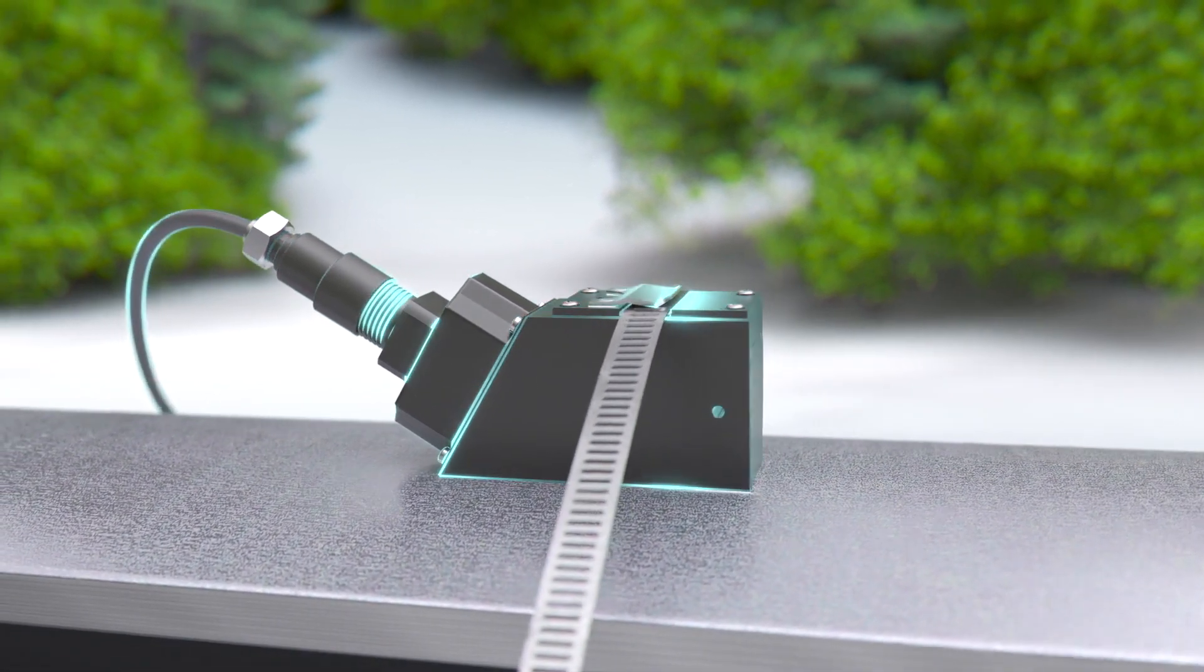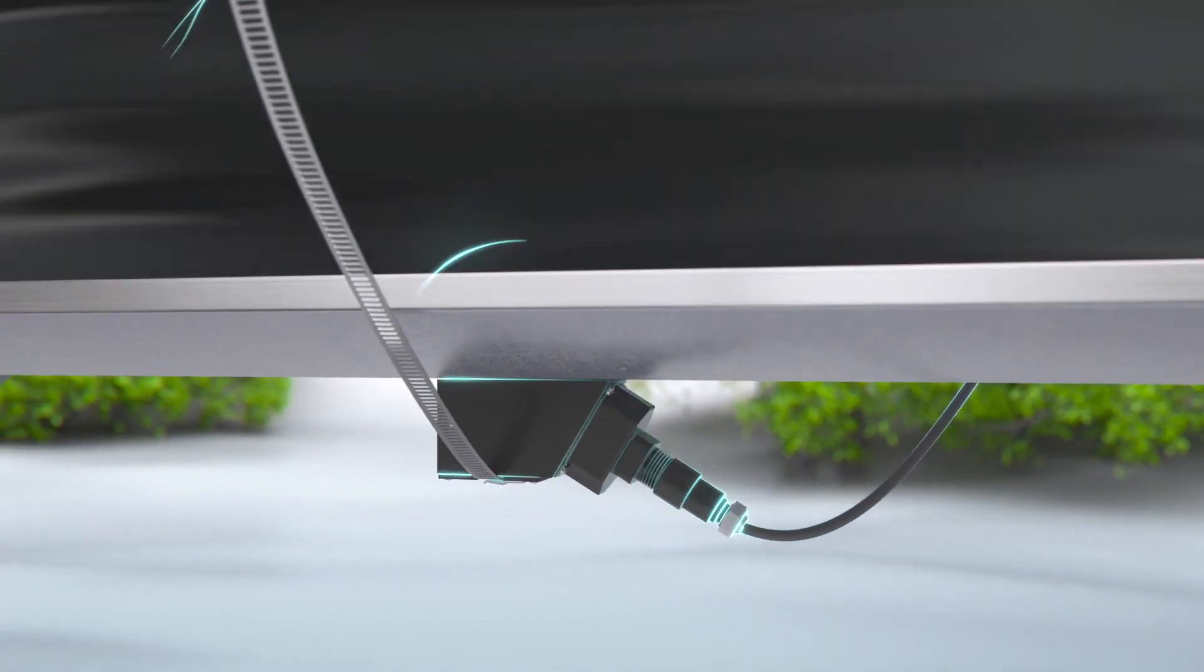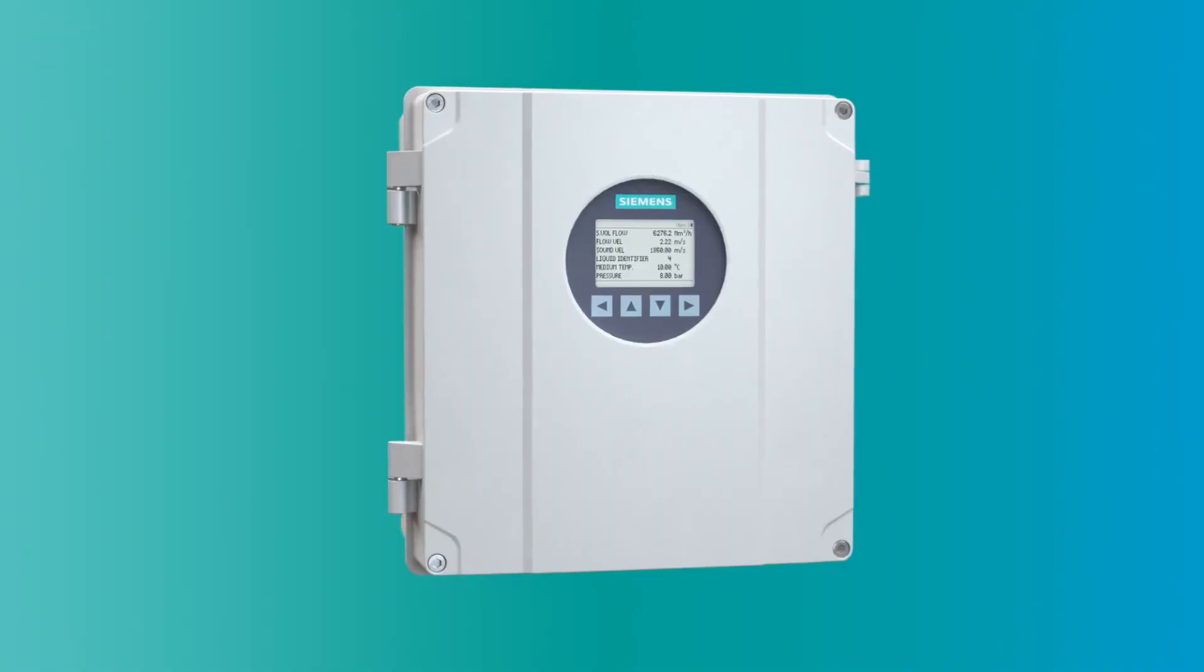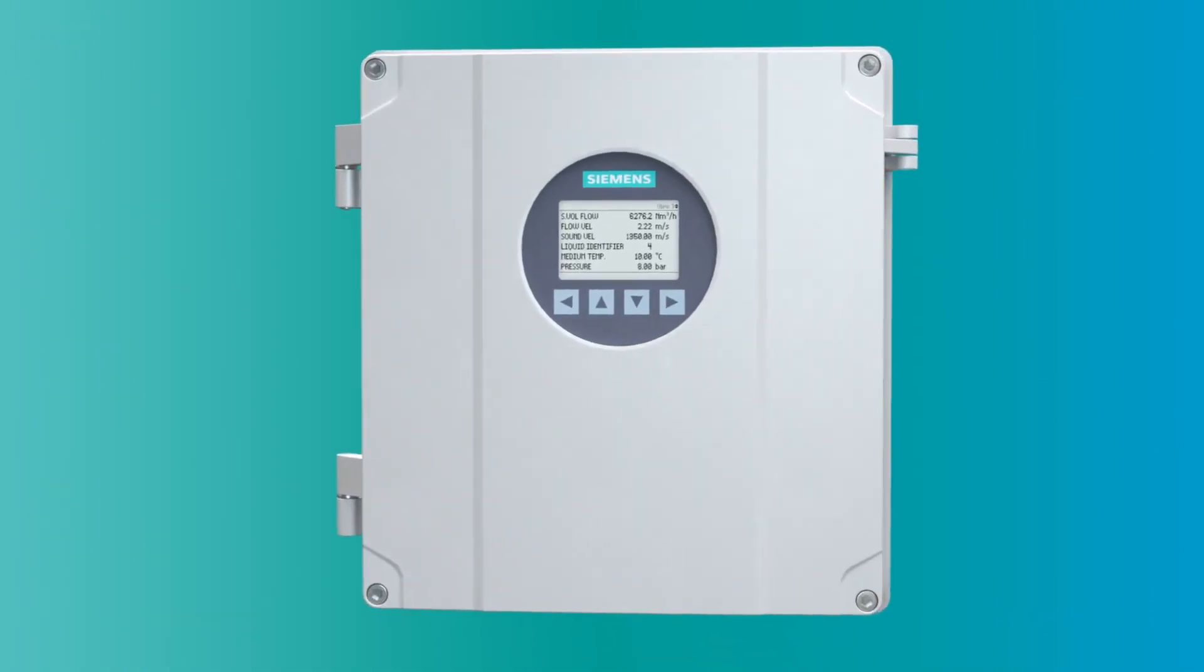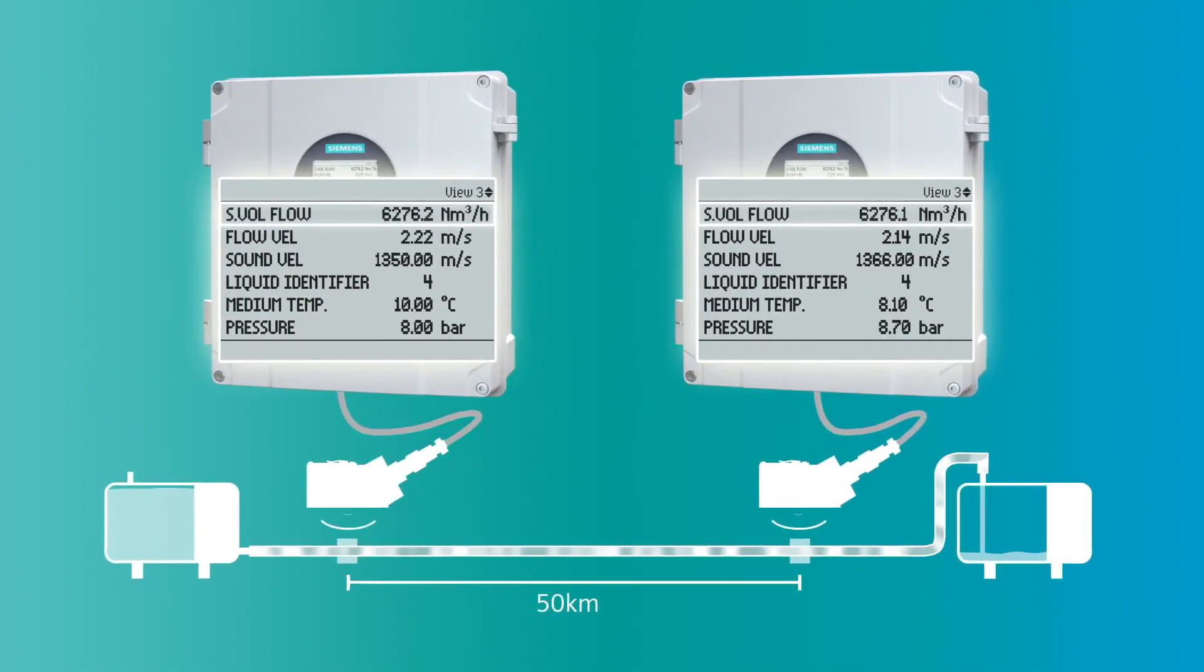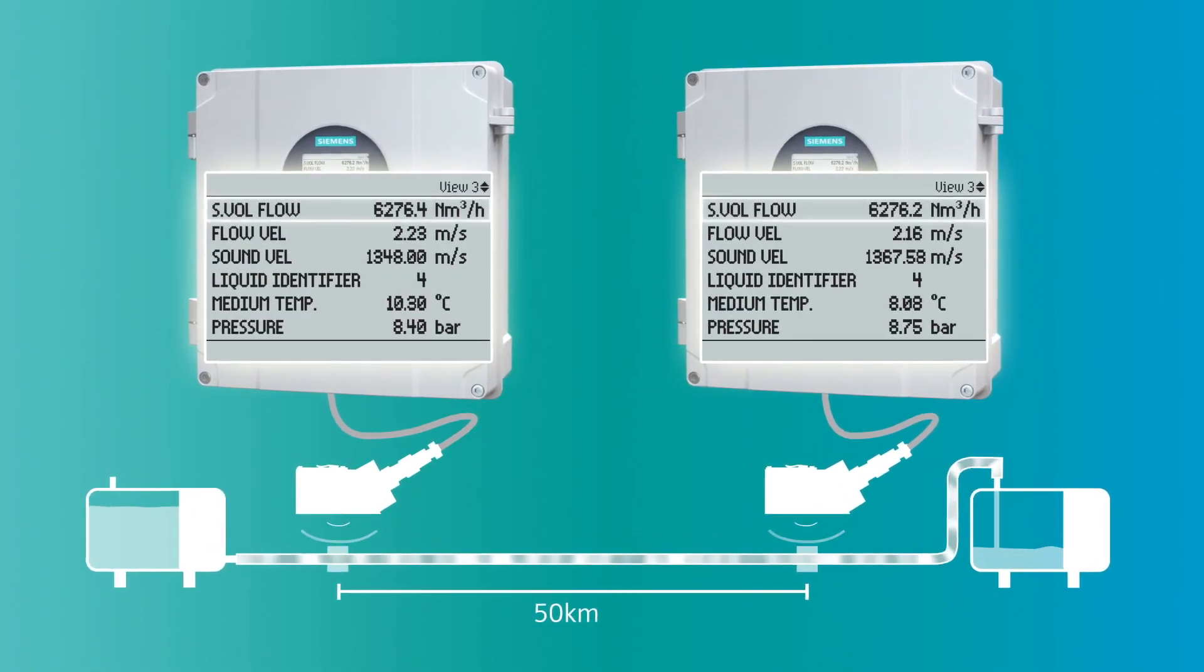SITRANS FS230 is accurate. Wide-beam sensors on the pipe transmit measuring signals in the resonance area of the pipe wall. The SITRANS FS230 digital transmitter processes these signals and automatically compensates for temperature, pressure, medium recognition and viscosity assignment.